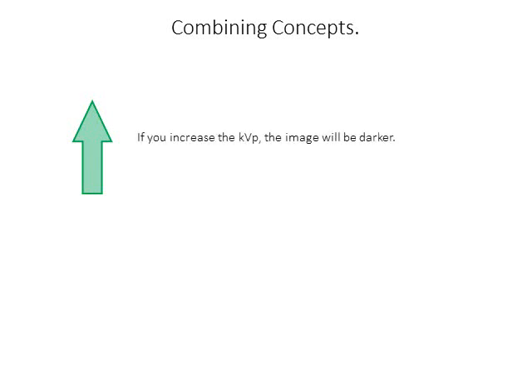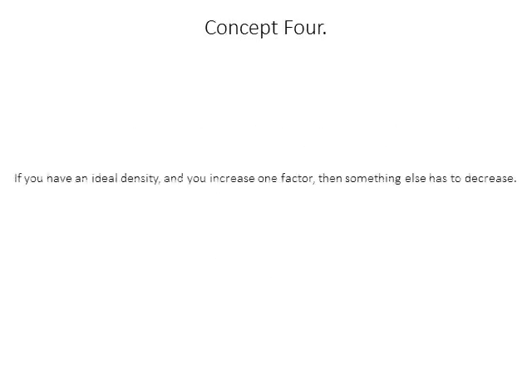To summarize: if you increase the KVP the image will be darker; if you increase the MAS the image will be darker; if you decrease the KVP the image will be lighter; if you decrease the MAS the image will be lighter. If your image has the perfect density and you want to achieve that same density at a higher KVP, you need to compensate by decreasing the MAS. If you increase one factor, something else has to decrease to maintain the same density.